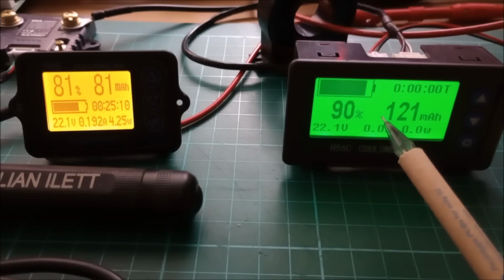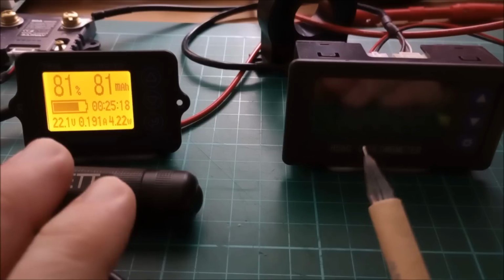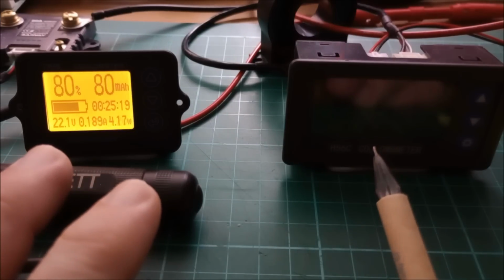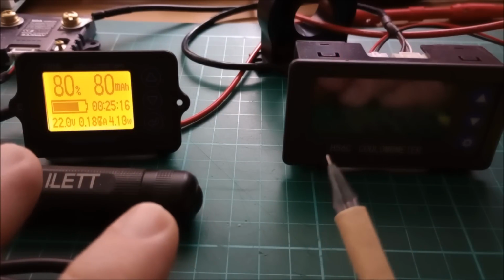It's not counting down, and it will just sit there at 90%. So you need to know that these have a minimum current required to initiate the counting up or counting down process - below that minimum current, they just don't count.